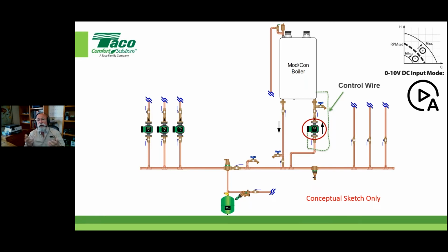Okay. And on the other side of the coin, if we see delta T's that are tighter than they should be, then let's slow that circulator down and get back into a lower return temperature and stop that water coming across these two T's that I spoke about earlier, right? And I'll get into that anyway. Understand that if you have the ability to do this, this is a good thing.